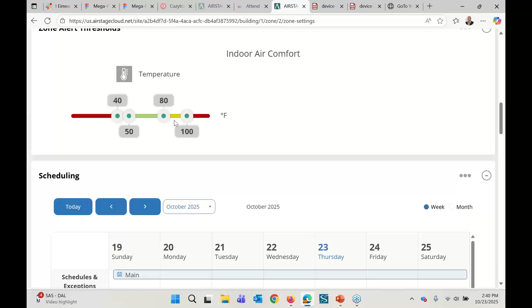Okay. So while we've been on here, if you saw when we started, the system was running. That system has now been put into standby mode. Standby mode means everything is running and working correctly, but the VRF is not actually running. All right. We have comfort thresholds. So if the temperature in the space ever gets above 80 degrees, it's going to send us an alert telling us that the VRF temperature is too high. If that temperature falls below 50, we're going to get an alert to tell us that it's too cold.